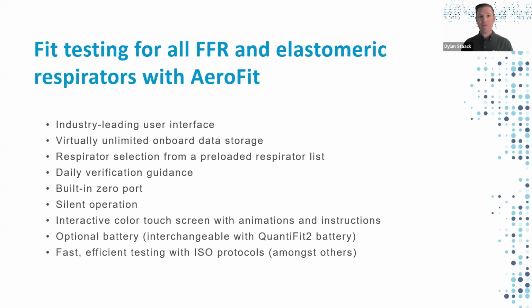In competing fit test instruments, the fit test administrator had to understand what technology they were using, had to understand the schematics of that, had to check the correct boxes, and then had to go through and complete two separate daily verifications. With our machine, all you have to do is tell us what respirators you are planning on testing that day, what types. We will then automatically execute the proper daily verification and walk you through each step so that all you have to do is connect the tube to the correct ports.